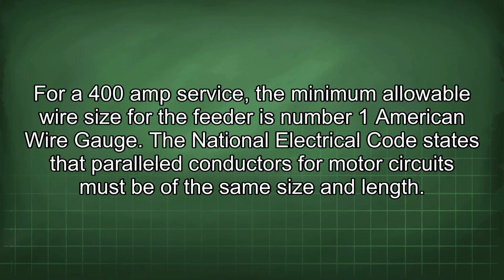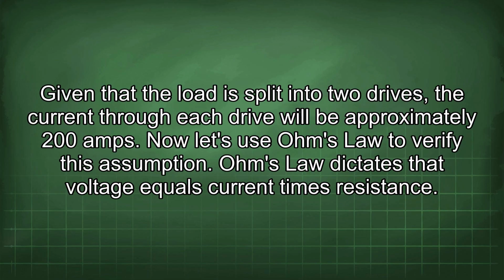For a 400 amp service, the minimum allowable wire size for the feeder is number 1 American wire gauge. The National Electrical Code states that paralleled conductors for motor circuits must be of the same size and length. Given that the load is split into 2 drives, the current through each drive will be approximately 200 amps. Now let's use Ohm's law to verify this assumption.